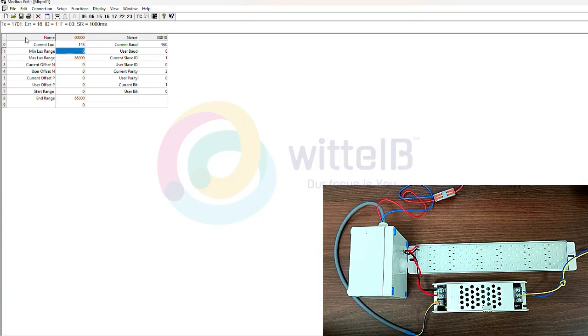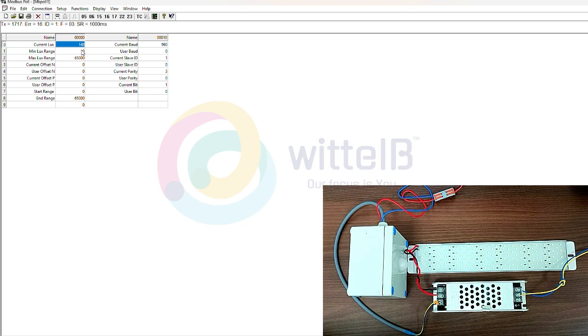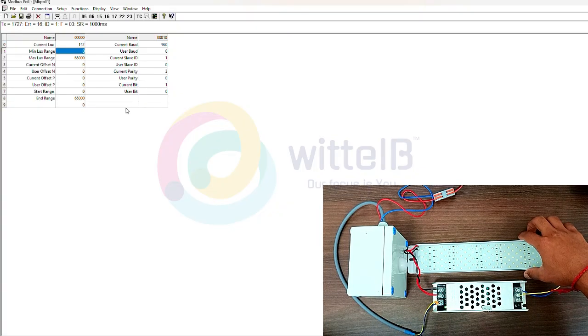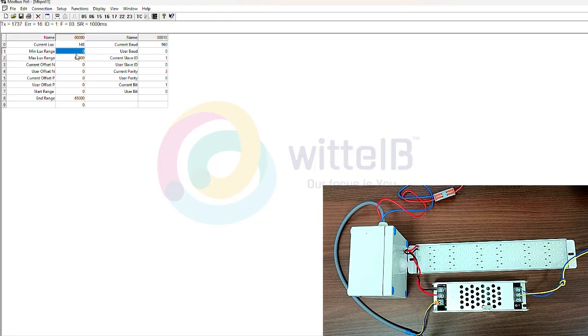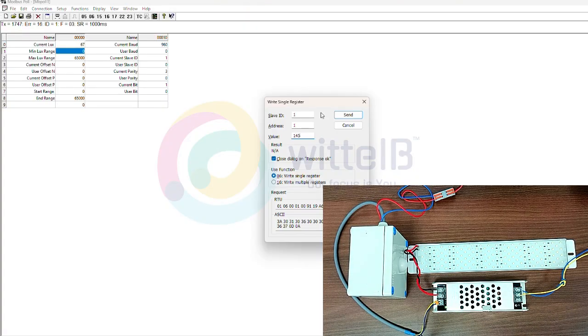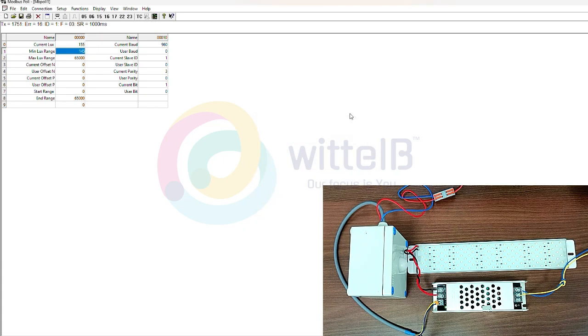Here I have provided names for the registers I have used for the particular specifications. At register 0 you get the current Lux value. Make it an unsigned integer, and you will get the Lux full intensity value. At the first register I am using the min range. First we need to calibrate the Lux. Without turning on the LED, I am getting a Lux value of 140 something, around 145 to 148. That means it is my minimum value, so this is my minimum Lux range. I will set this 145 as the minimum Lux range.